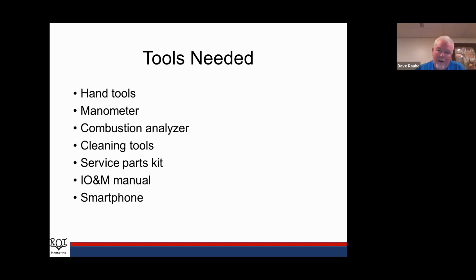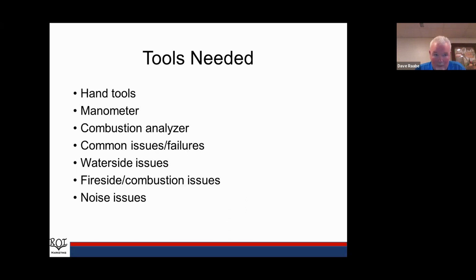So tools you need if you're going out to work on a condensing boiler. You're going to need your hand tools. A lot of the condensing boilers use Torx bits. There's a lot of metrics on them, so you probably want a set of maybe small and large metric Allen keys, some screwdrivers, like I said, Torx bits, and then you're going to need a manometer. So this can be a digital manometer. It can be a U-tube. You need something to be able to measure gas pressure. You need a combustion analyzer.